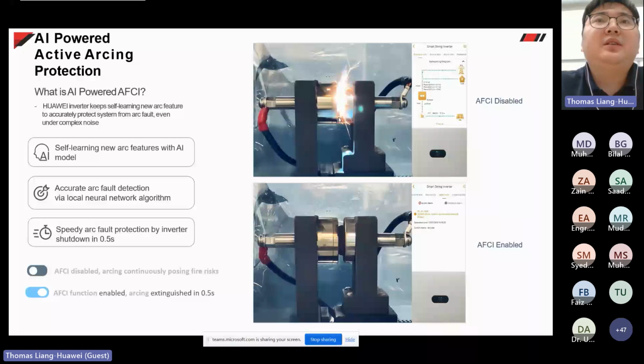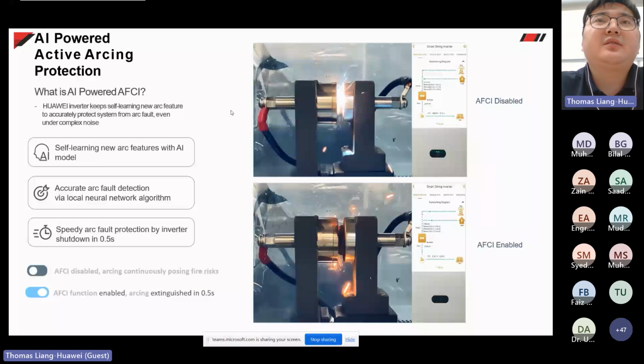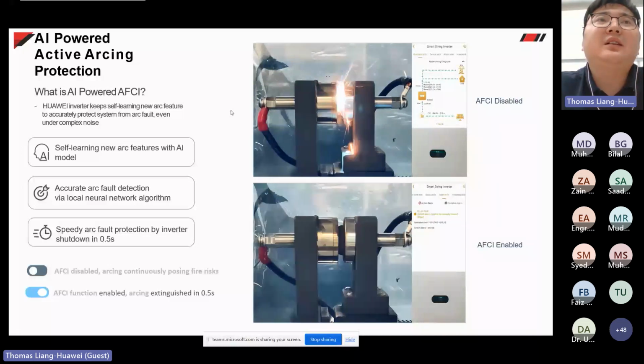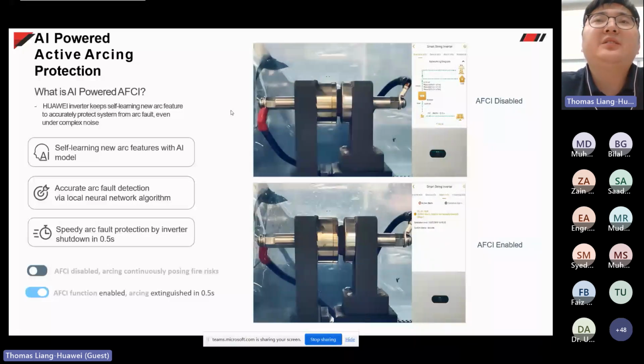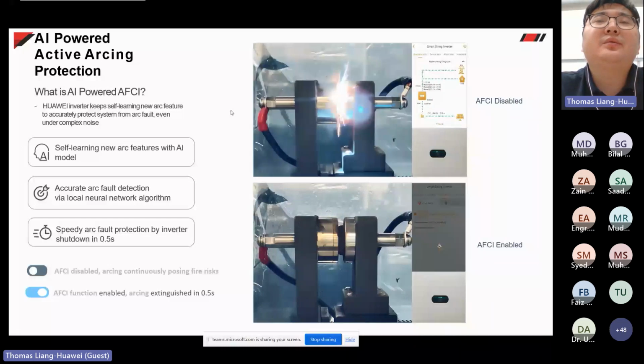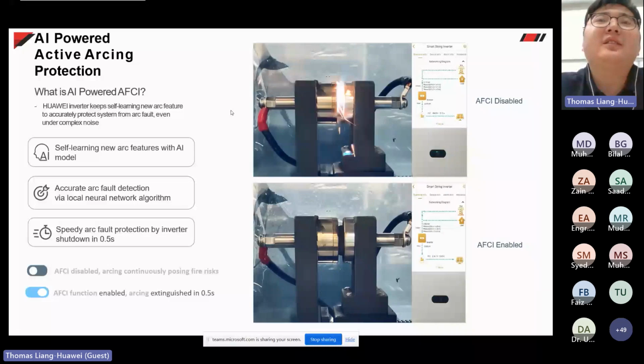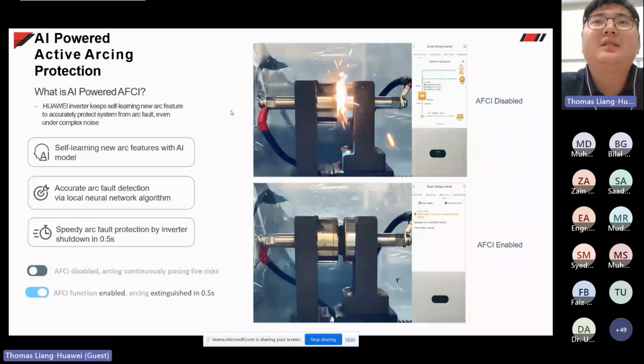So Huawei developed a self-learning algorithm for these features, and the AFCI function is built into the inverter. No matter when the fault happens, the inverter will detect it, and if it confirms that an arc fault happened, it will stop the system within 0.5 seconds.